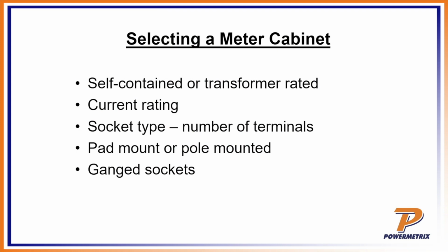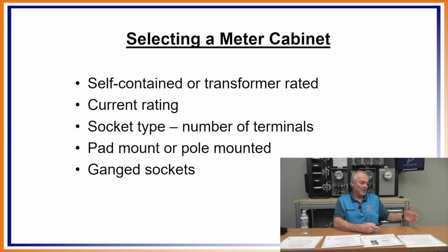So selecting a meter cabinet, you got self-contained or transformer rated, of course, as we said in the very beginning. That's going to dictate what kind of cabinet. The current rating, it's always important. We keep seeing that, right? Because the current rating is the delineator between self-contained and transformer rated, right? So the second one affects the first one. So once I know what current rating I have, then that's going to be one of the keys to tell me self-contained or transformer rated.